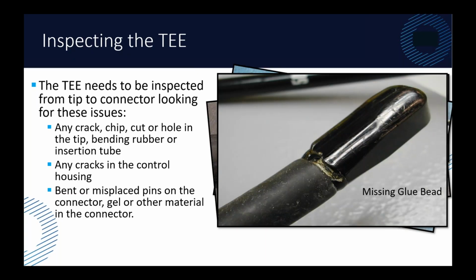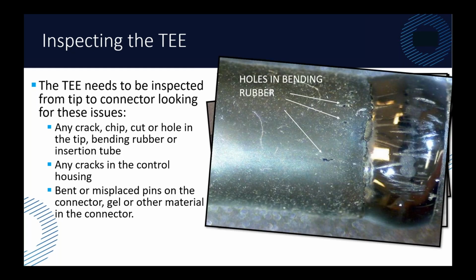Glue bead is missing. What's really bad about when glue beads go missing is they don't just fall off as a hole, they crack and chip. And so you get these areas where it's really difficult to clean. That's not glue, folks. That's foreign body material. That's material from the previous patient. Now, luckily, the Cidex tends to kill all the bad things that are in there, but it's still disgusting. Holes in the bending rubber. This is blown up significantly. These would be very difficult to even see without a magnifying glass.